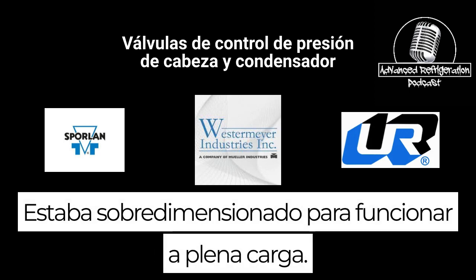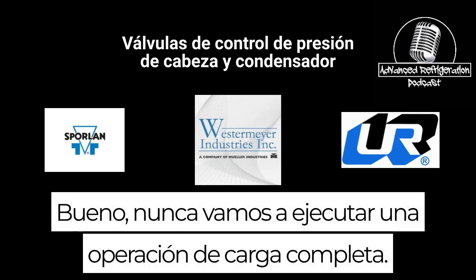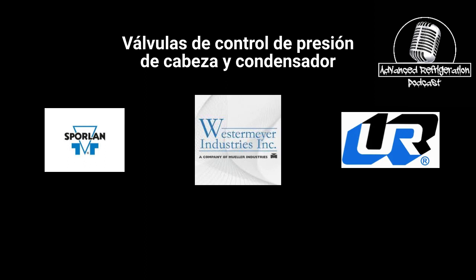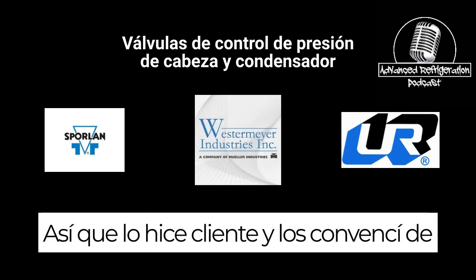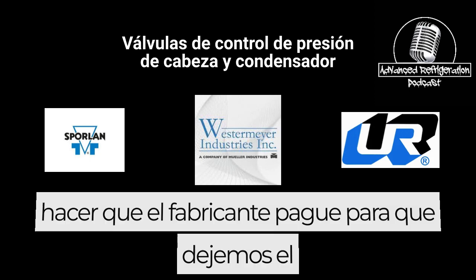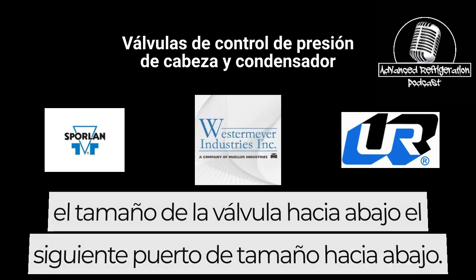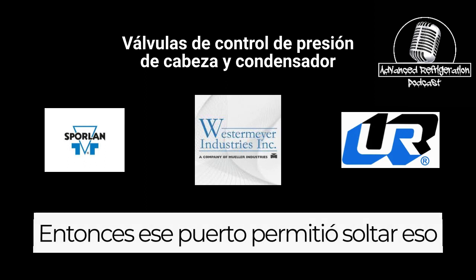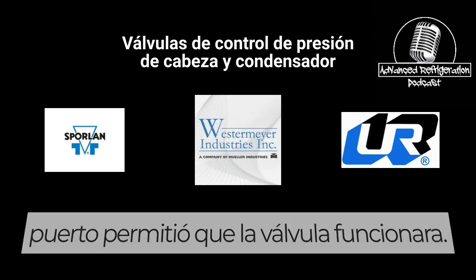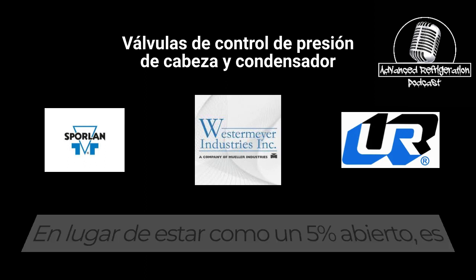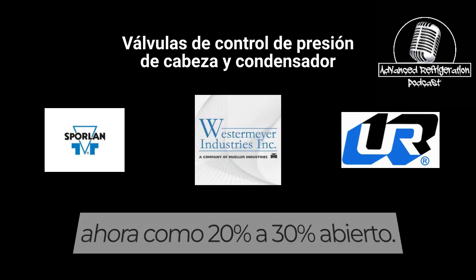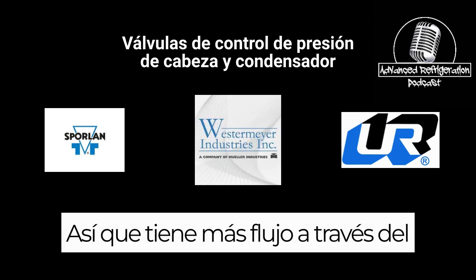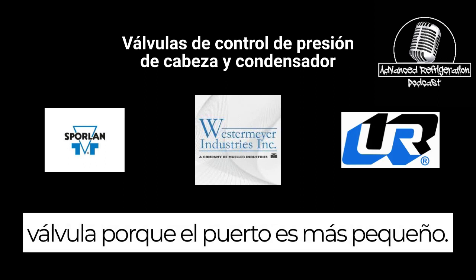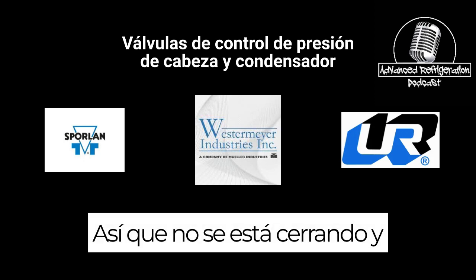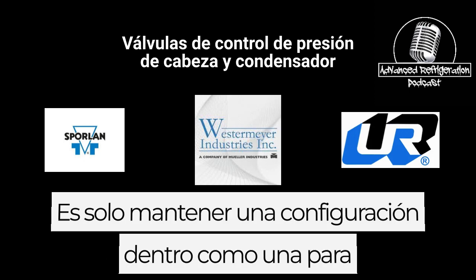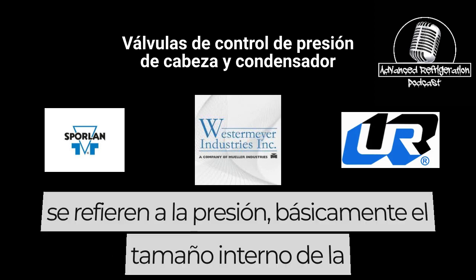It was oversized for full load operation, and we're never going to run full load operation. So we talked to the customer and convinced them to make the manufacturer pay for us to drop the valve size down, the next size port down. Dropping that port allowed that valve to operate instead of being like 5% open, it's now like 20-30% open. So it's got more flow through the valve because the porting is smaller. So it's not shutting and opening. It's not hunting anymore. It's just holding a setting within like 1 to 2 PSI.